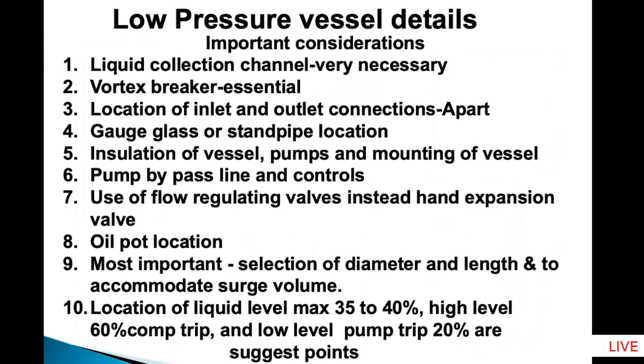Important considerations: a liquid collection channel is very necessary so that no liquid enters the compressor. Vortex breaker essential. Location of inlet and outlet connections should be as far apart as possible. Gauge glass or standpipe is required. Insulation of the vessel and pump mounting vessels is essential. Bypass line for the pump is required. Use of flow regulating valves instead of hand expansion valves is recommended. Oil pot location is important. Selection of diameter and length to accommodate surge volume.